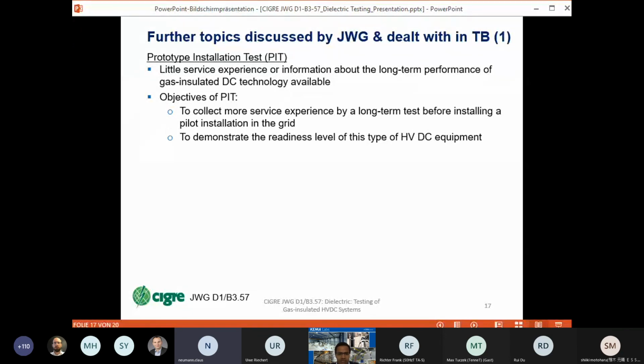As a matter of fact, there is little service experience or information about the long-term performance of gas-insulated DC technology available, so this test is reasonable. The objectives are to collect more service experience through long-term tests before installing a pilot installation in the grid, which should be the next step, and to demonstrate the readiness level of this type of HVDC equipment. I think that was also the basis for the promotion project.